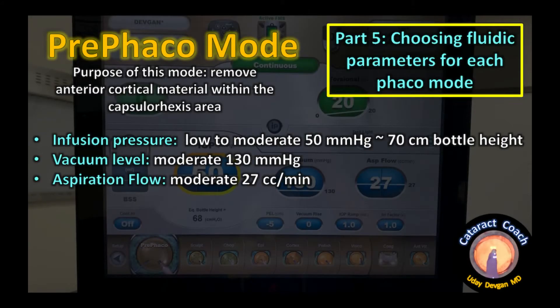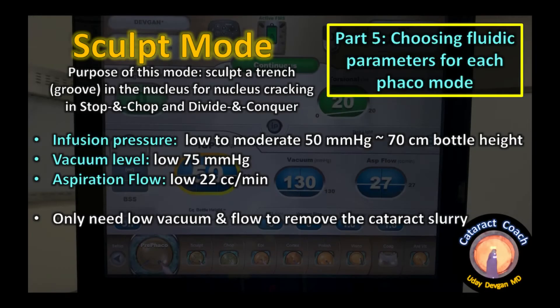Now reviewing the settings: Pre-phaco mode removes anterior cortical material within the capsulorhexis area, using low to moderate infusion pressure, moderate vacuum, and moderate aspiration flow. Sculpt mode sculpts a trench or groove in the nucleus for cracking, stop-and-chop, and divide-and-conquer techniques — requiring low infusion pressure, low vacuum, and low flow, just enough to remove the cataract slurry.